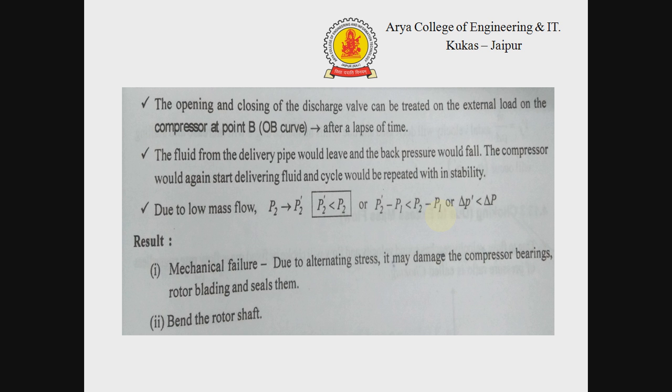Due to this phenomenon the following results are obtained. There will be a mechanical failure due to alternating stress. It may damage the compressor bearings, rotor blading and seals, and bend the rotor shaft.